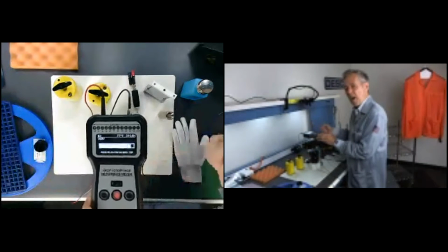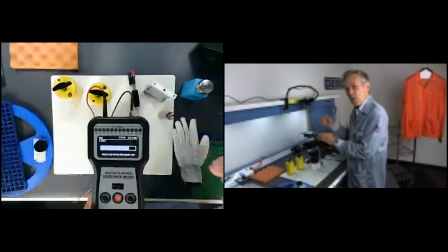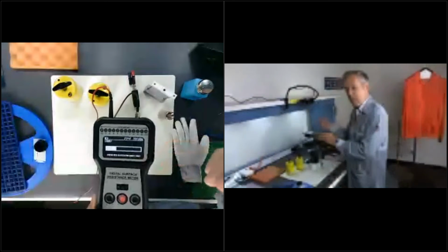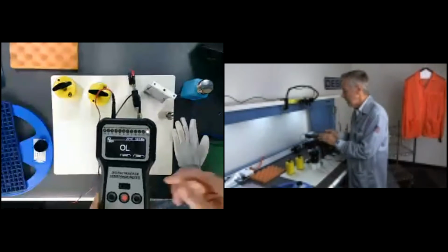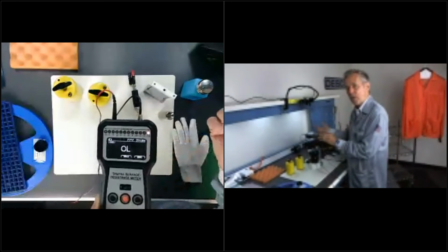So notice the white bar. That's when we're starting to get up over that 10 to the 12th resistance number, okay? Now I'm going to let that go, but I can also override it, which I'm going to show you in a minute. So let me let this go through because we need all that extra time and voltage. OL, so that means it's over the limit.